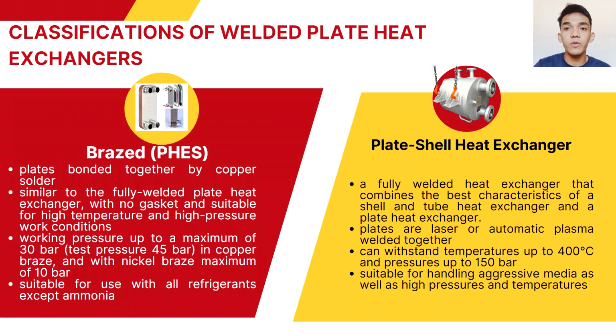So, these are evolution of detachable heat exchanger with the sealing material changed from a rubber pad to copper. And all the plates are welded or bonded together by a copper solder. So this ensures a tight fit of all contact points, resulting in high heat exchange efficiency and the ability to withstand pressure, thus achieving a long service life. So the copper brazed plate heat exchanger is similar to the fully welded PHE. So same sila na with no gasket and suitable for high temperature and high pressure work conditions. Pero katulad ng fully welded, it cannot be repaired or cleaned easily.